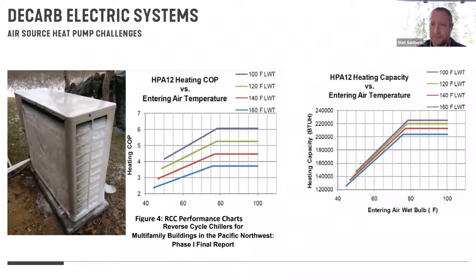and can decline to the point where it's not cost effective to pick that equipment because of the cost of energy. The other trouble that we have with air source heat pumps at low ambient outside temperature is that the actual energy production of that unit is also dropping with the outside air temperature. And if we're sizing that heat pump for wintertime conditions, we're sizing for that near worst case outside air temperature. And so we're buying more heat pump than we really want to buy, because the performance under those poor outside air conditions is a fraction of what the full unit capacity could be.